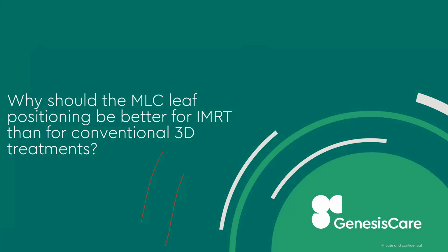Okay. Why should the MLC leaf positioning be better for IMRT than for conventional 3D treatments? Positional accuracy, reproducibility is more important for IMRT, while for 3D CRT, that's important, but it's comparatively less.